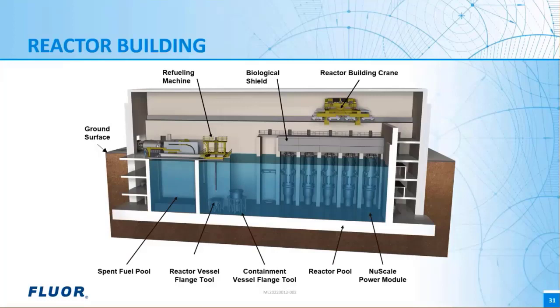As I previously mentioned, the power modules can be installed in the reactor building after construction of the building is complete. And this keeps fabrication and installation off the critical path of construction. And the power modules can be installed by the operating crew of the plant. They don't need to be installed by the construction contractor. Moving the power modules around is done the same way as they'll be moved around during refueling once you're inside the reactor building.